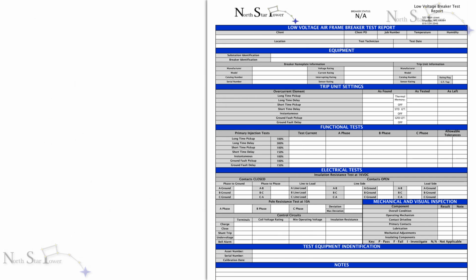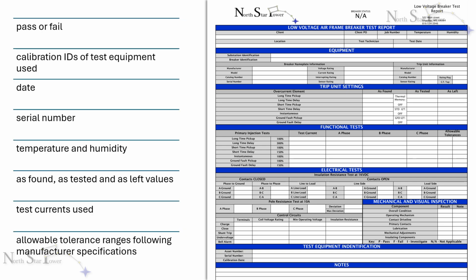For each tested sticker, the plant should also have test sheets to match. The sheets should clearly indicate pass or fail, calibration IDs of the test equipment, the date, serial number, temperature and humidity, as found, as tested, and as left values, test currents used, and allowable tolerance ranges following manufacturer specifications. A test sheet that is missing information is cause for alarm that the testing technician was untrained or failed to fully follow standard procedures.